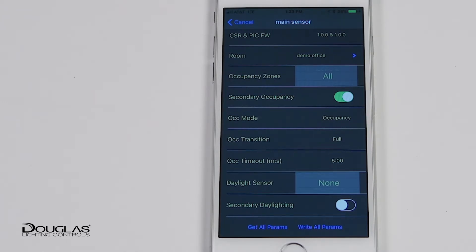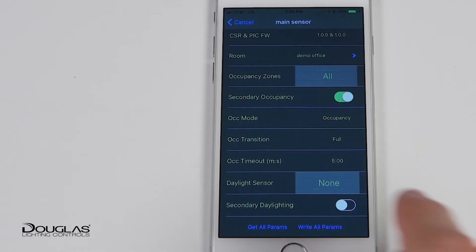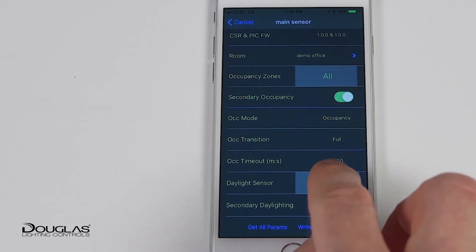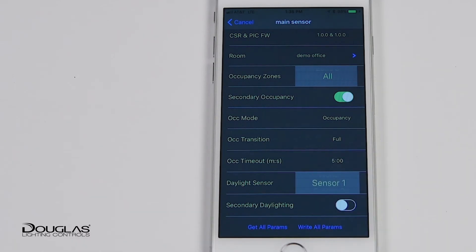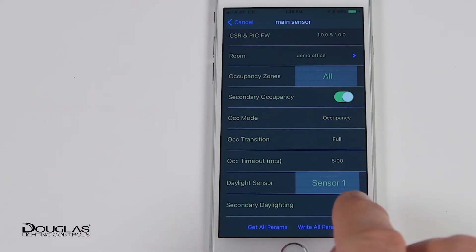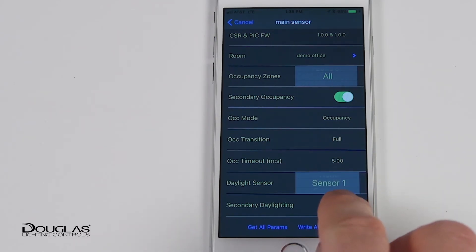The device can be assigned as the primary or secondary daylight sensor to create two daylight zones in a room. Secondary daylighting enables ratio dimming between the first and second daylighting zones in a room.